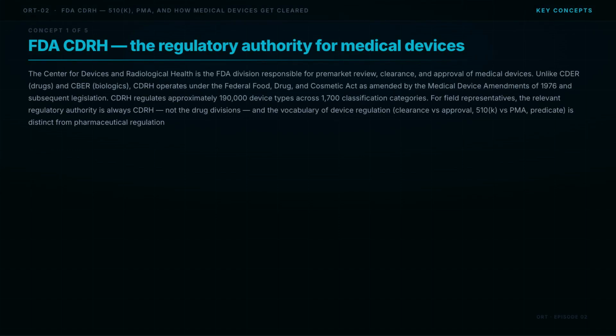FDA CDRH, the regulatory authority for medical devices. The Center for Devices and Radiological Health is the FDA division responsible for pre-market review, clearance, and approval of medical devices. Unlike CDER drugs and CBER biologics, CDRH operates under the Federal Food, Drug, and Cosmetic Act as amended by the Medical Device Amendments of 1976 and subsequent legislation. CDRH regulates approximately 190,000 device types across 1,700 classification categories. For field representatives, the relevant regulatory authority is always CDRH, not the drug divisions.